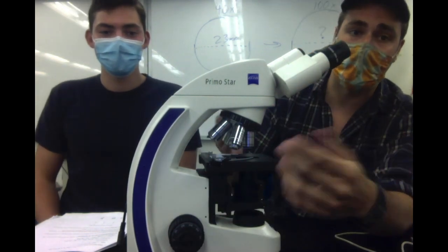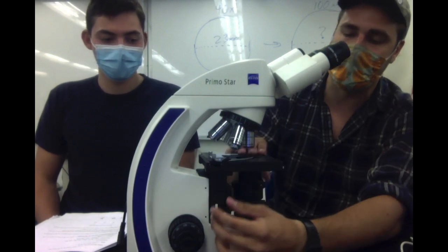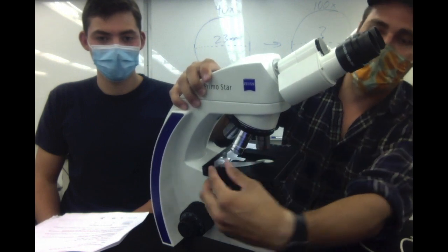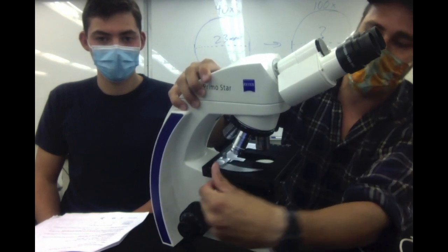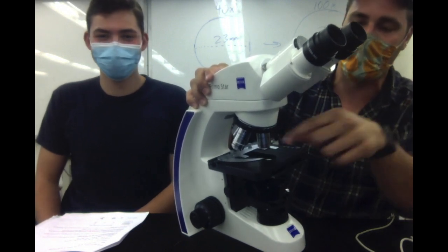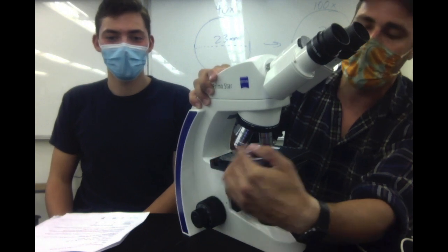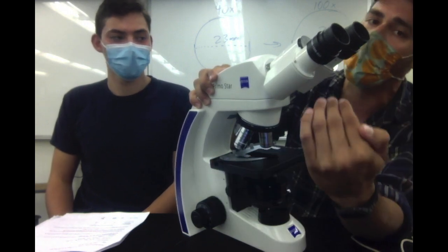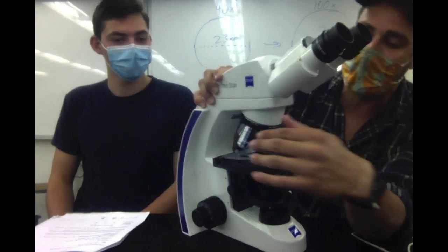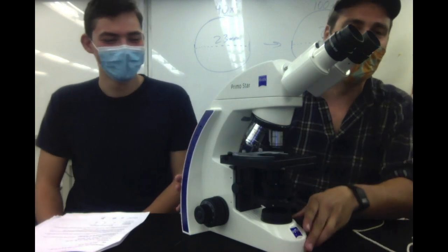Let's talk about where you put your sample. Whenever you put a sample on the stage, I'm going to angle this towards you guys. All you have to do is move the stage arm down and place the sample into these slide grooves right here. Then make sure that you slowly close the arm back on the slide, and make sure that the arm isn't sliding below or above the slide. Just don't do that, and it goes super smooth from there.